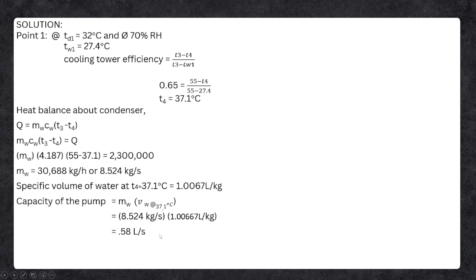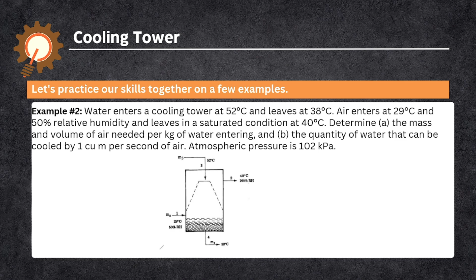For example number 2: Water enters a cooling tower at 52 degrees Celsius and leaves at 38 degrees Celsius. Air enters at 29 degrees Celsius and 50% relative humidity and leaves in a saturated condition at 40 degrees Celsius. Determine the mass and volume of air needed per kilogram of water entering, and the quantity of water that can be cooled by 1 cubic meter per second of air. Atmospheric pressure is 102 kilopascals.